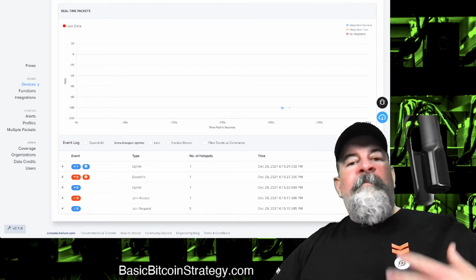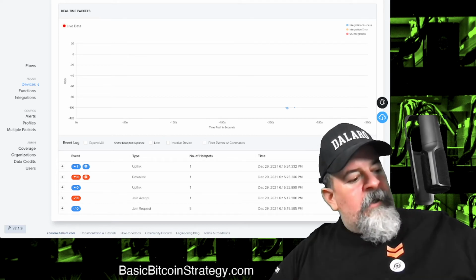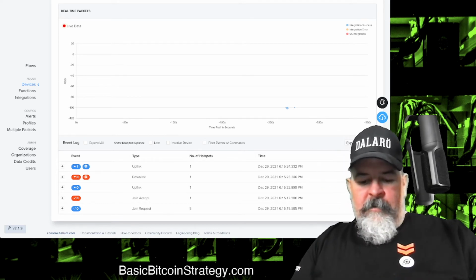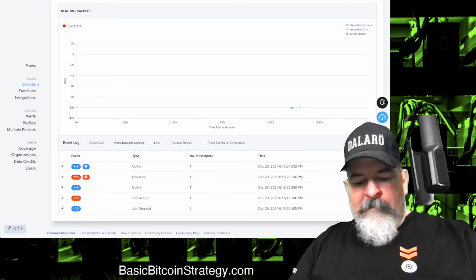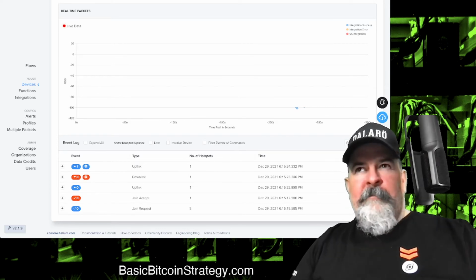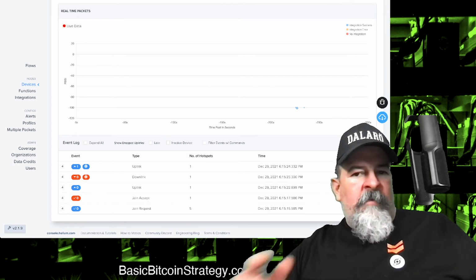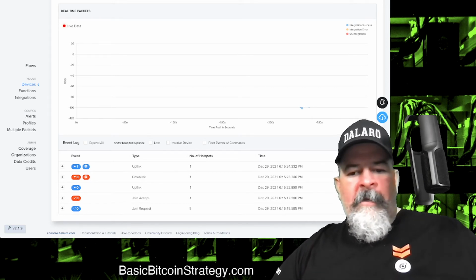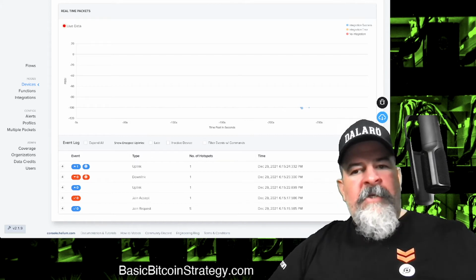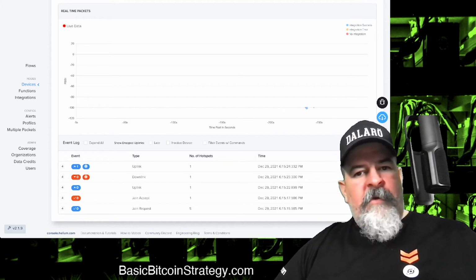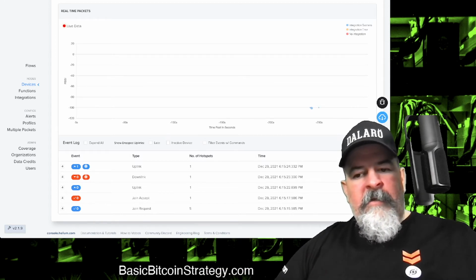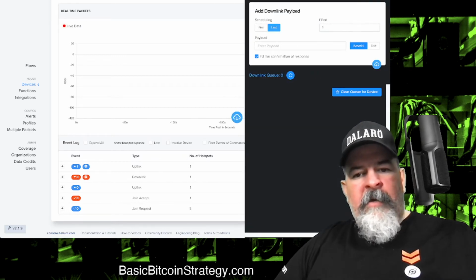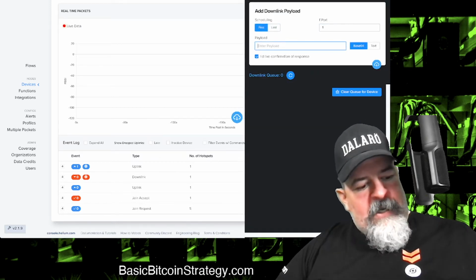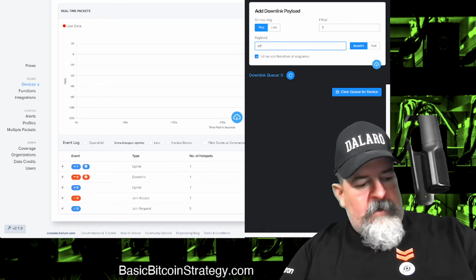But let's pretend I wanted to send a command to change that to 60 seconds. I've already worked this out - there's some documentation, you go in and come up with a hexadecimal value for the number you want to put in. I would configure my payload here, and in this case, for 60 seconds, it's going to be 0100.